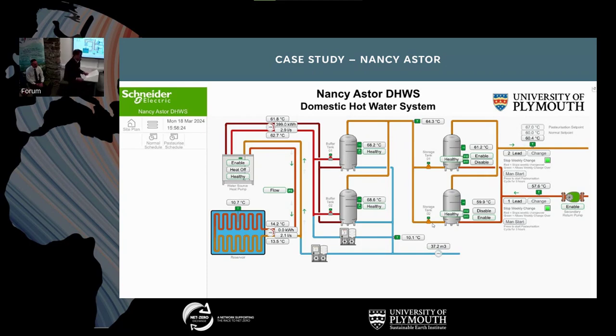So in summary, does it work? Well, yes, it does, and it's actually performing really well, as Brad has already suggested. We commissioned the system on the 18th of January this year, which ironically was the coldest day of the year. It was minus 4 degrees that day, and the reservoir was completely iced over on the day of commissioning. However, by the end of the commissioning process on that same day, we were actually producing water output from the heat pump at around 60 degrees C, which truly exceeded our expectations.